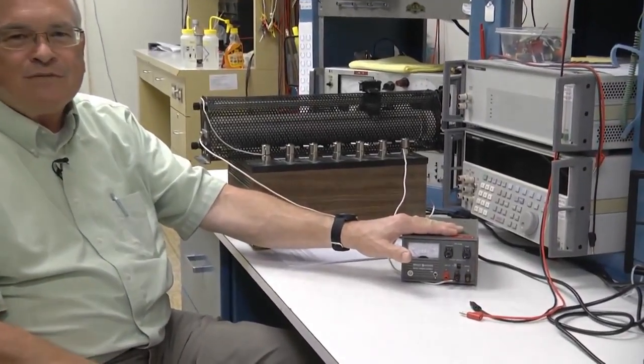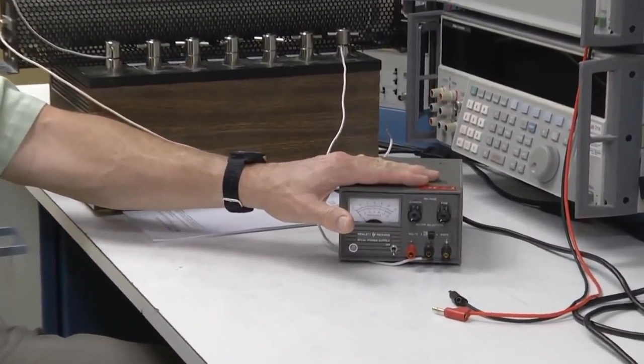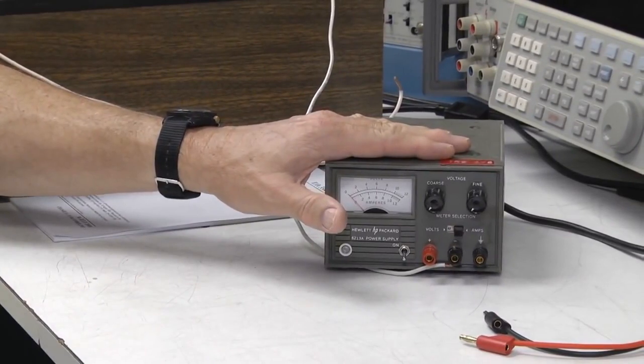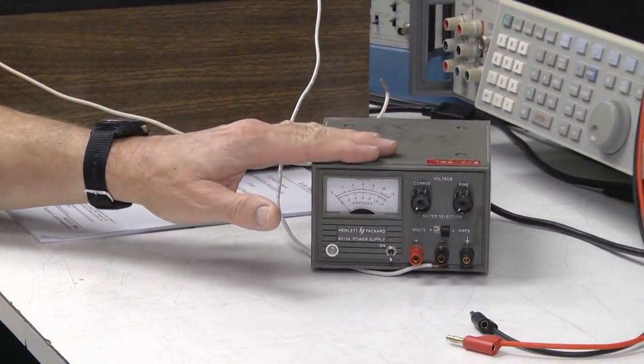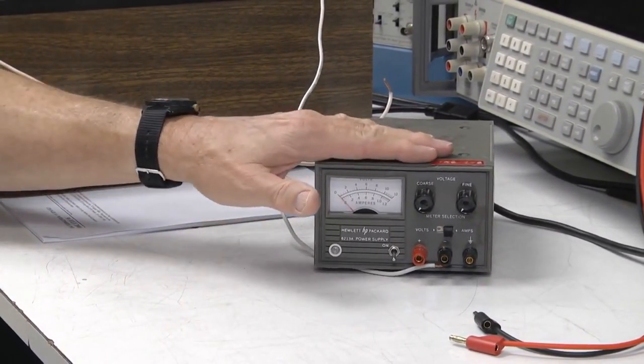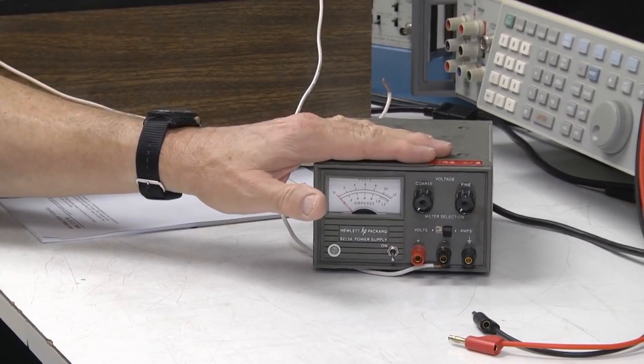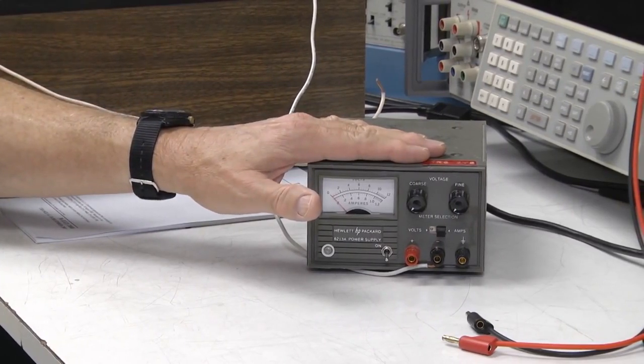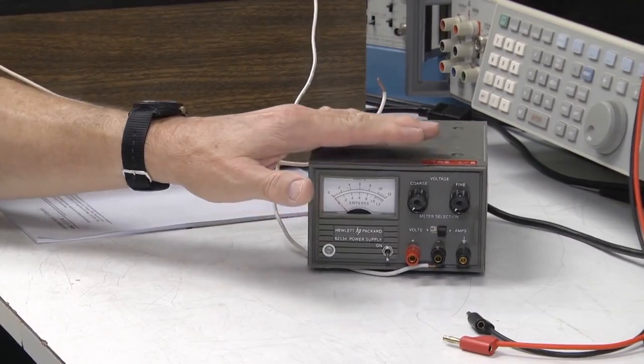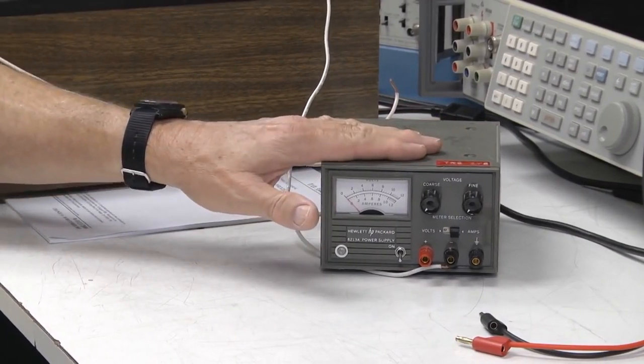This is representative of a typical DC power supply that comes in for calibration at Boise Calibration Service. The parameters that are calibrated on this are the DC voltage output meter, the DC current meter, and then we'll also be checking for AC ripple when the power supply is loaded down. This is the representative of the power supplies.